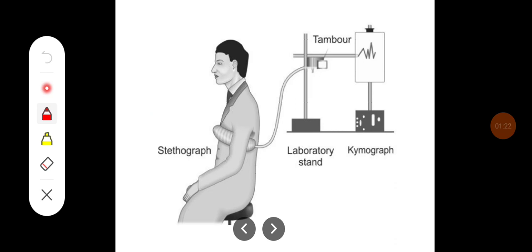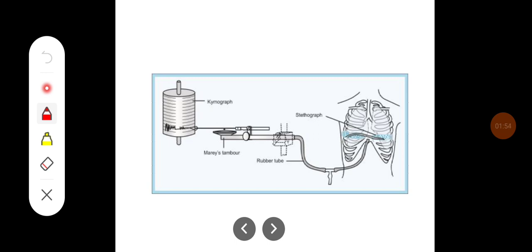As you can see, the stethograph is tied over the chest. When the person inspires, the volume in the corrugated tube increases and pressure decreases, creating a negative pressure in Marey's chamber. That is how the lever moves in a downward direction, so inspiration is always recorded as a downstroke. When the chest expands, the negative pressure created in Marey's chamber records a downward deflection on the moving kymograph, and vice versa.